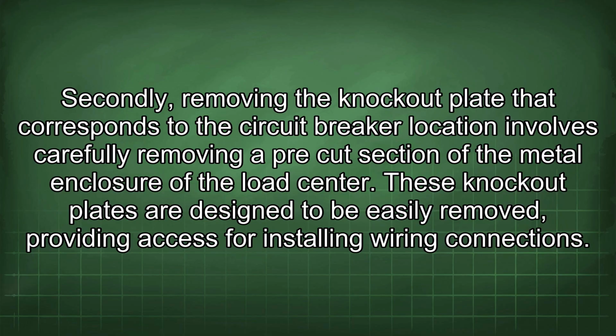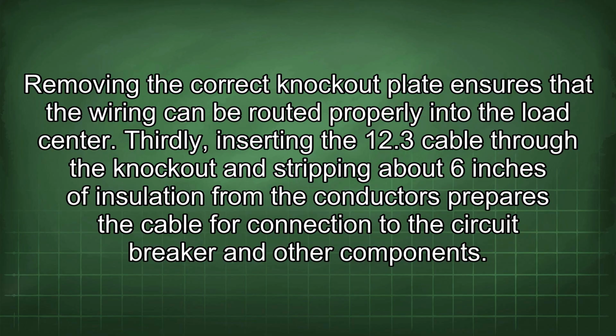Secondly, removing the knockout plate that corresponds to the circuit breaker location involves carefully removing a pre-cut section of the metal enclosure of the load center. These knockout plates are designed to be easily removed, providing access for installing wiring connections. Removing the correct knockout plate ensures that the wiring can be routed properly into the load center.